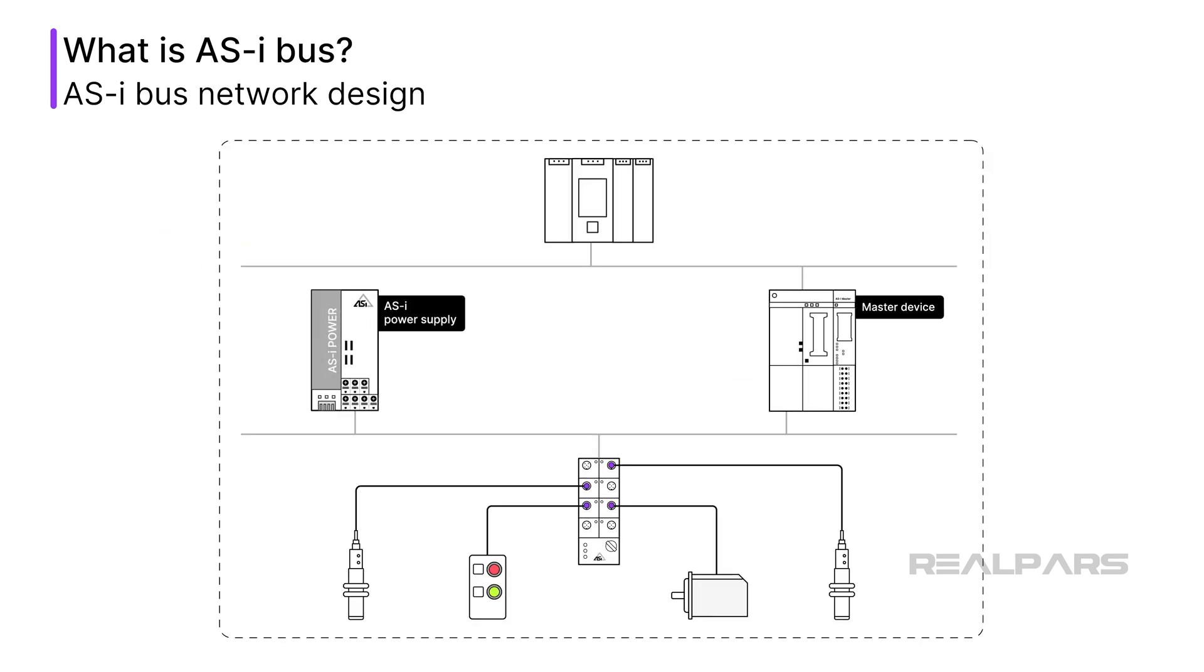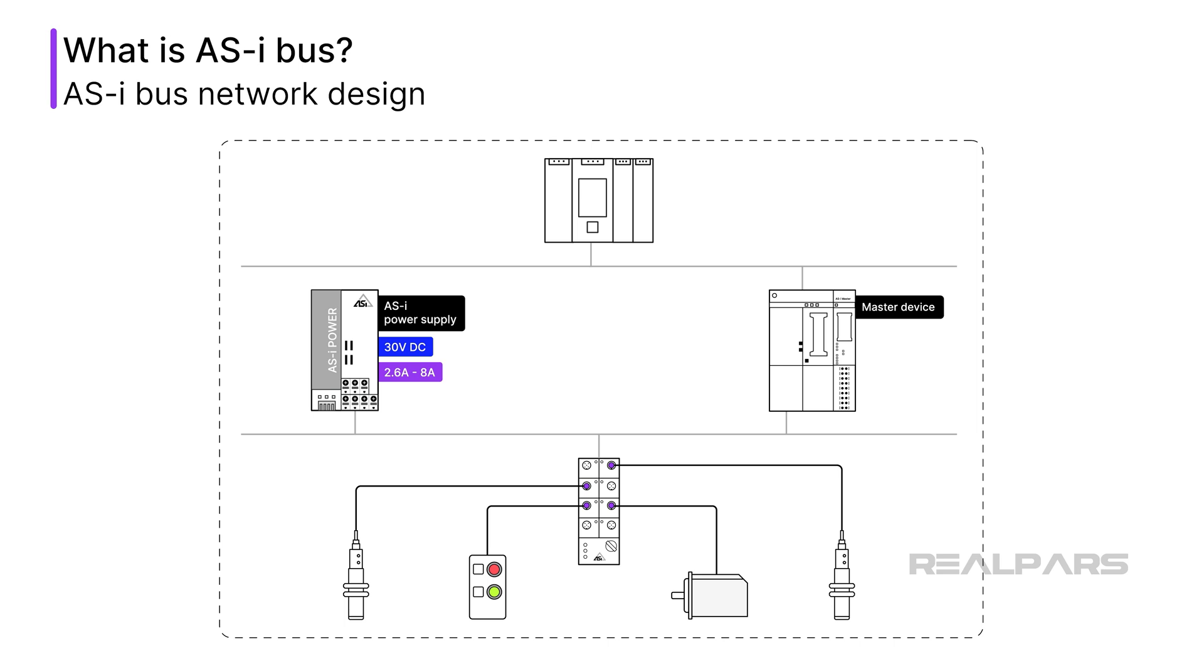An AS-i bus power supply typically provides power at 30 volts DC, with varying amperages from 2.6 to 8 amps. An AS-i bus power supply provides internal circuitry that aids in decoupling the data signal from the power signal. The power supply size is chosen to match the load on the segment. Typical AS-i bus devices draw 30 to 40 milliamps, allowing many devices to reside on a single segment.